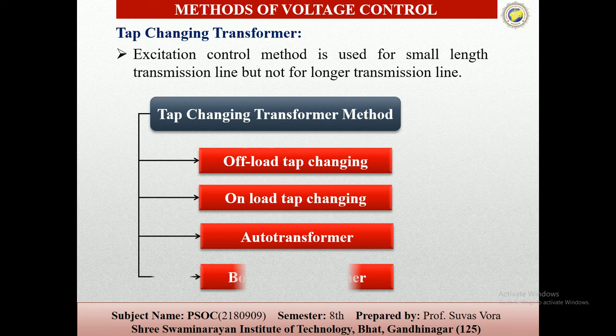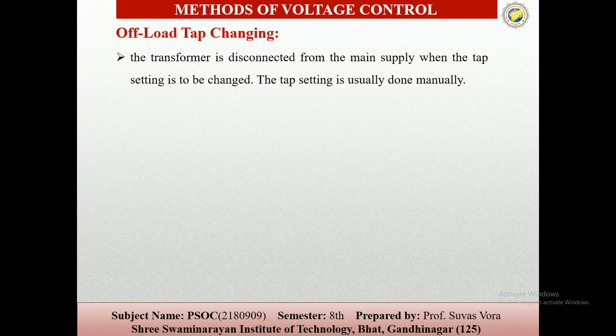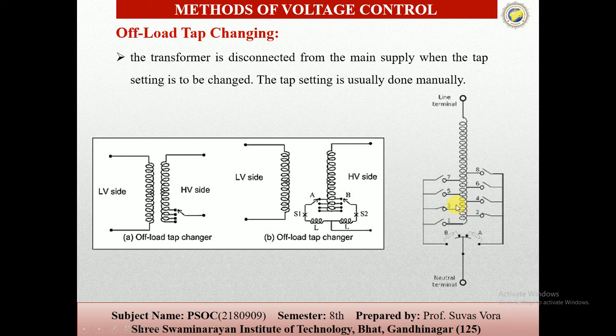So now start with the off-load tap changing. We have already studied this in the transformer systems. So the off-load tap changing means no supply is connected, that is, it is disconnected from the main supply when the tap setting is to be changed, and this is done manually. You can see here these are the taps, and these are the other constructions from the tapping. So these are the working of the off-load tap changing conditions. Here the switch is closed and opened.